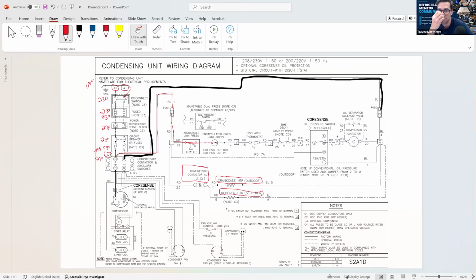So this could be like a Johnson Controls one. You might see a little blue one. There's lots of different brands out there. I think Penn has some. So as we travel through, if that's closed, if we're below 400 PSI, we'll keep going down, and then we go down to terminal 2. Then as we go through terminal 2, we have a discharge thermostat in it. So we would be going through that to terminal 3.